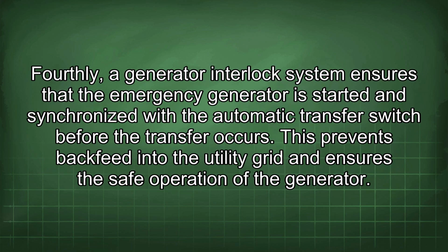Fourthly, a generator interlock system ensures that the emergency generator is started and synchronized with the automatic transfer switch before the transfer occurs. This prevents backfeed into the utility grid and ensures the safe operation of the generator.